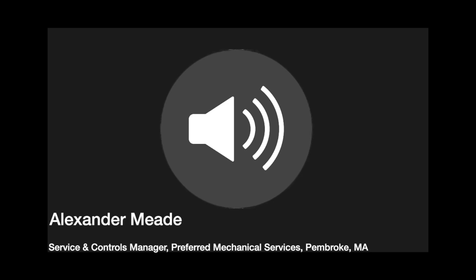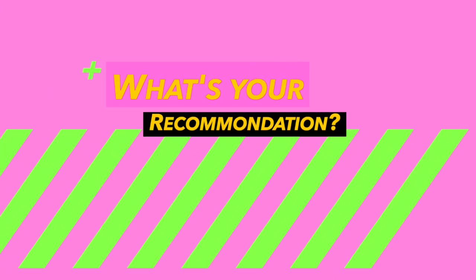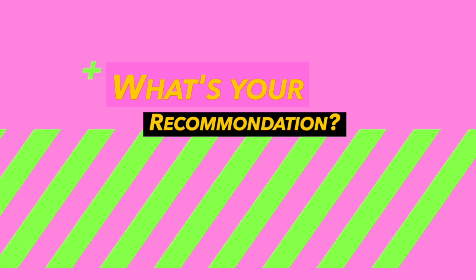And then, depending on how it's used and the control scheme, the sequence it's put in place, if you use it to trigger compressors to turn on, you'll find that it inherently will cause erroneous energy consumption because it'll react to what it thinks is the surface temperature. But it doesn't allow for a flywheel effect of the compressors and the glycol to reclaim the ice temperature after resurfacing. So, what is your recommended way of running a rink?